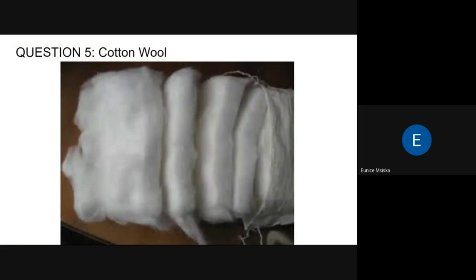Gross particle filters are spongy, allowing air to pass through easily. Cotton wool, however, is not as porous, so using it instead will restrict airflow into the unit, reducing the amount of air compressed by the compressor. Additionally, the compacted pores of cotton wool can easily become clogged by debris, completely blocking airflow and affecting oxygen concentration since there won't be enough pressure for the nitrogen adsorption process.